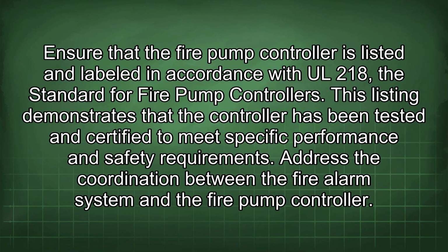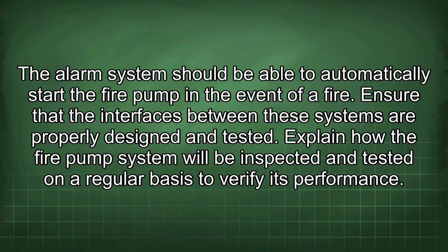Address the coordination between the fire alarm system and the fire pump controller. The alarm system should be able to automatically start the fire pump in the event of a fire. Ensure that the interfaces between these systems are properly designed and tested.